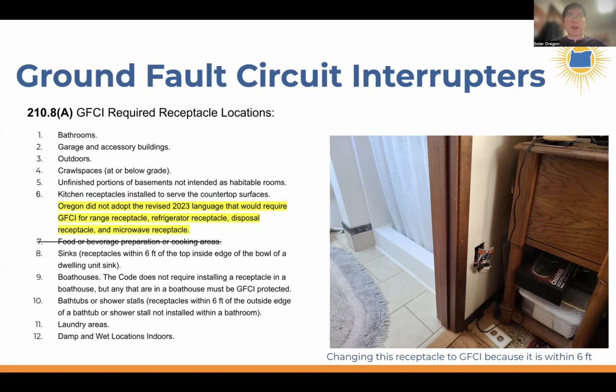Somebody really wanting to use an electrical device inside the shower while it's still warm—maybe on a winter day, you step out of the shower and it's very cold, so somebody wants to use a hair dryer while in the shower. But it's a wet location, so somebody got shocked, and an investigation into that incident found that a GFCI would have protected that person.